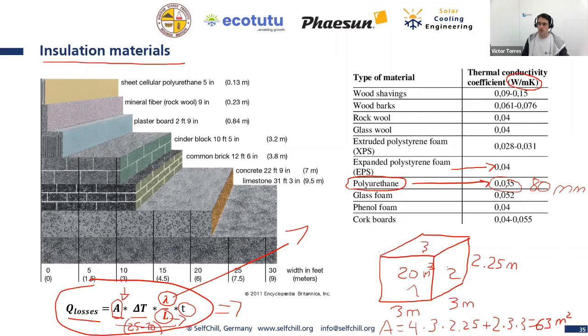Then we have 0.035 for thermal conductivity, and the thickness of 80 millimeters should be in meters, so 0.08. Who can do this equation? I'll do it in parallel: 63 times 15 degrees times 0.035 divided by 0.08. Here you go: 413 watts. And if we multiply that by 24...